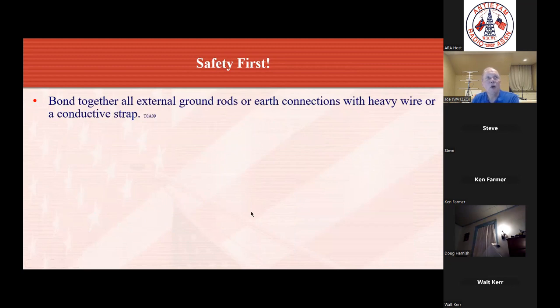Safety, safety, safety. Bond together all external ground rods or earth connections with heavy wire or a conductive strap. You want to make sure you're using high quality, heavy wire for that, not a very fine wire. For these connections, you want lots of surface area on the metallic surfaces, which is why conductive straps are so popular.